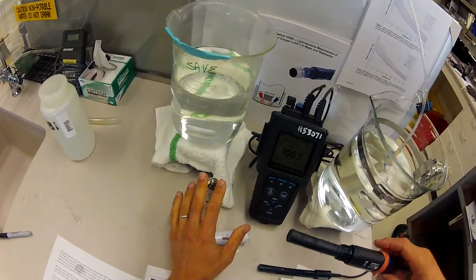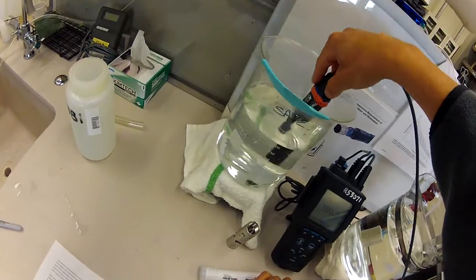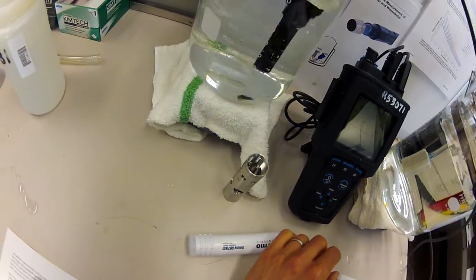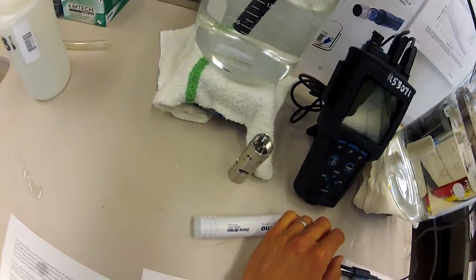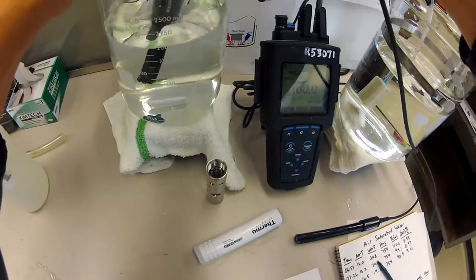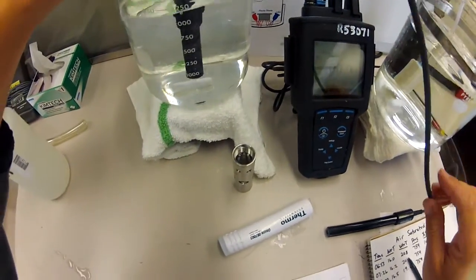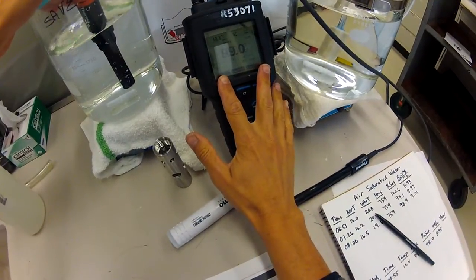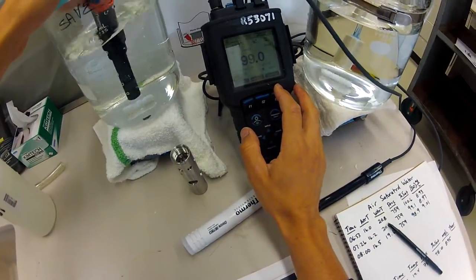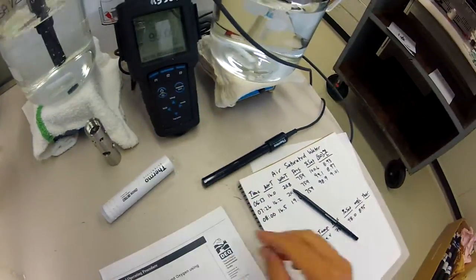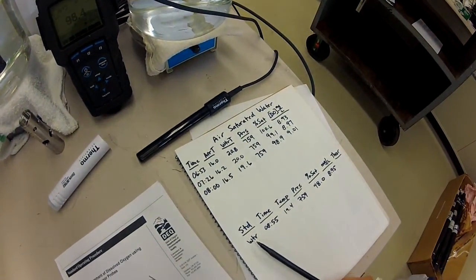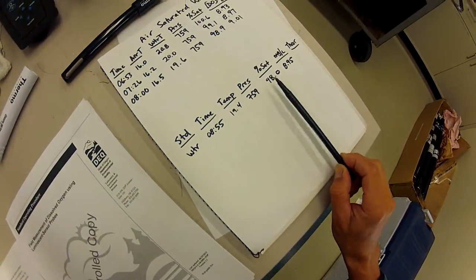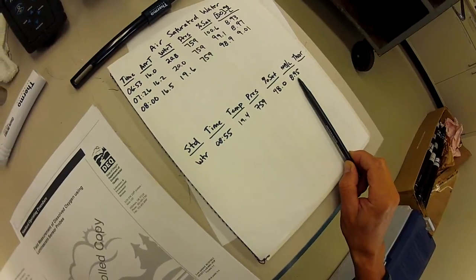I'm going to go ahead and not use the guard here and just be careful with the probe. The guard does take a little bit longer to equilibrate temperature-wise, it can slow things down. I do recommend using it in the field. I'm just going to wait for the temperature to equilibrate here. Then I will record what I get in my water standard - time, temperature, pressure, percent saturation, and milligrams per liter.